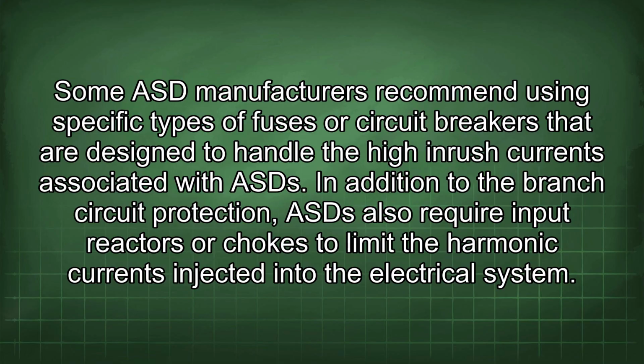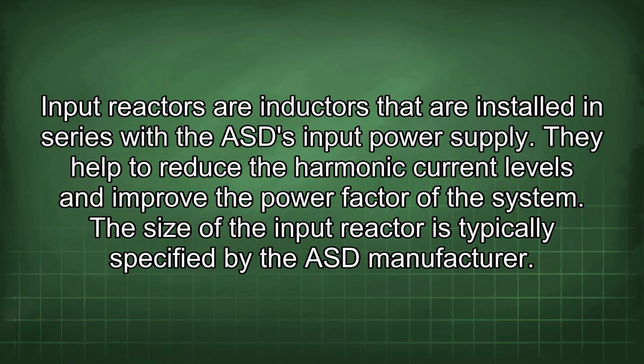currents associated with ASDs. In addition to the branch circuit protection, ASDs also require input reactors, or chokes, to limit the harmonic currents injected into the electrical system. Input reactors are inductors that are installed in series with the ASD input power supply. They help to reduce the harmonic current levels and improve the power factor of the system. The size of the input reactor is typically specified by the ASD manufacturer.